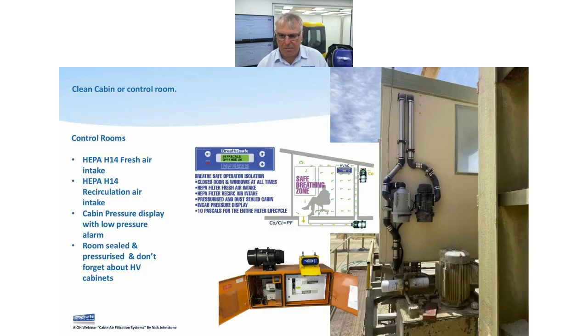Here's the way to go for a control room: two units on the right-hand side. The black unit is a fresh air filtration unit giving positive pressurization — stopping more dust from getting in. Most places that we're talking about are going to be hot, so they've got aircon. As the aircon cools the room down, it drops the pressure, so you always need something making up that pressure — that's why you always need a fresh air pressure isolator. The little gray unit is our recirculation unit, drawing air from under the operator's boots through a floor grill, cleaning it, and returning it. Clean air comes in the top, drops over the breathing zone, is sucked out through the floor, re-cleaned, and comes back around — by far the most effective way of keeping the breathing zone clear.